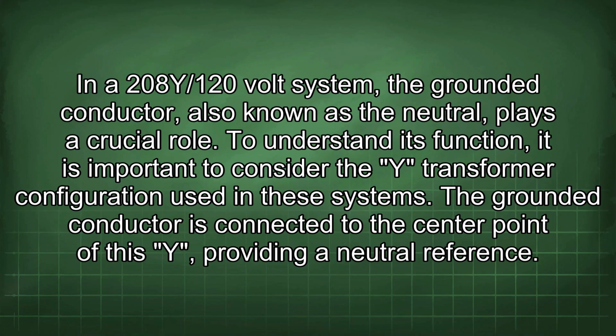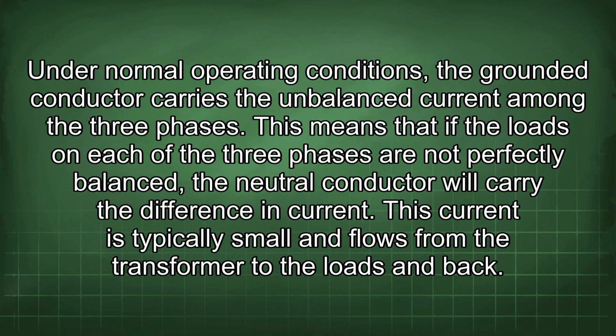In a 208Y/120 volt system, the grounded conductor, also known as the neutral, plays a crucial role. To understand its function, it is important to consider the Y-transformer configuration used in these systems. The grounded conductor is connected to the center point of this Y, providing a neutral reference. Under normal operating conditions, the grounded conductor carries the unbalanced current among the three phases.